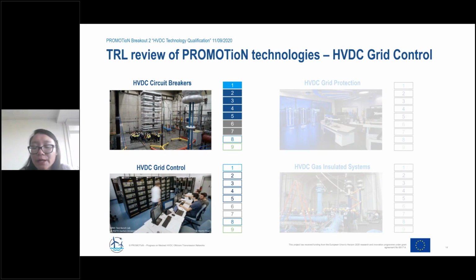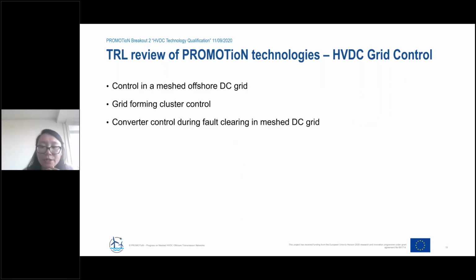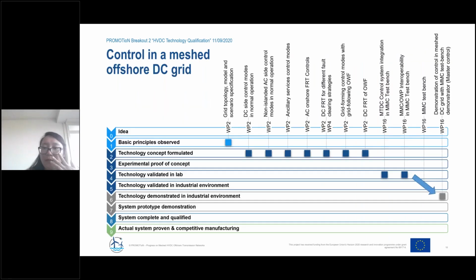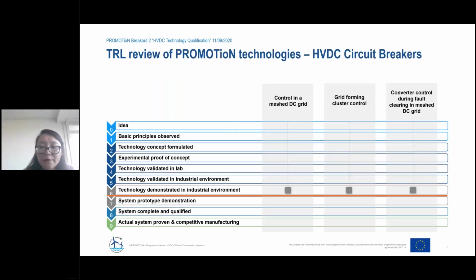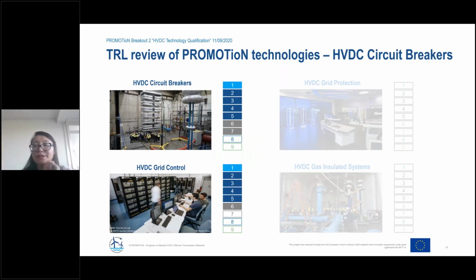So then we look at the HVDC grid control, which is an algorithm-based technology. We have assessed different sub-technologies of grid control in a meshed DC grid. With the demonstration of control in a meshed DC grid using the MMC test bench demonstrator, the TRL advanced to level 6. For the other two sub-technologies, grid forming cluster control and converter control during fault clearing in the meshed DC grid, they also acquired a TRL 6. So the TRL of HVDC grid control is reviewed as level 6.